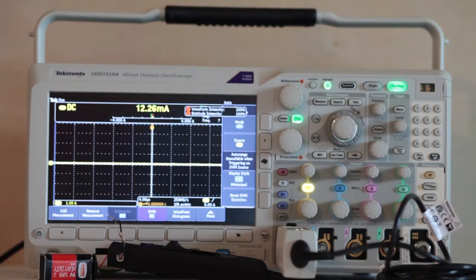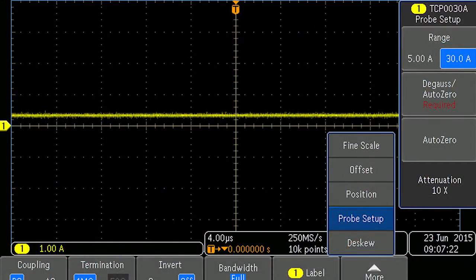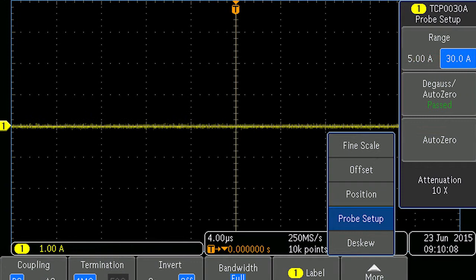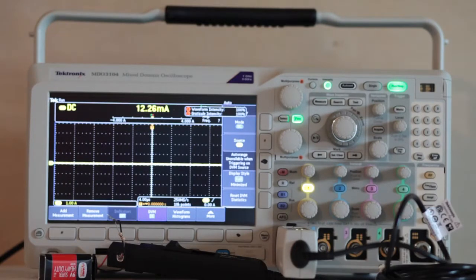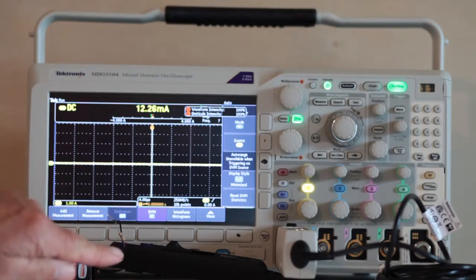When connected to the oscilloscope, a window opens in the display and it will alert you to degaussing. Simply press the degauss button on the probe and the residual magnetism is eliminated. In doing this, there should be either no conductor in the jaws or an unpowered conductor in the jaws. Moreover, for degaussing to take place, the jaws must be not only closed but locked. Otherwise, error messages rather than degaussing will occur. Now we are ready to use the current probe.